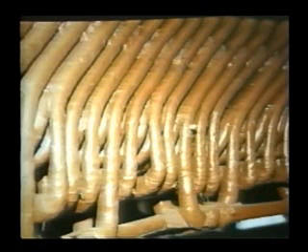Now, the original equipment had an asphalt flake mica insulation system, and this has another type of system which is not thermoplastic and is more mechanically rigid, but at the same time, the question would be, is this stiffness of this insulation system by itself sufficient to warrant the decrease in the number of blocks and ties that were used on this particular machine? Because, as you're well aware, blocking and tying and bracing is a very labor-intensive operation, which requires many man-hours in a large machine, or even a few hours in a small machine, and that can make the difference between the cost being within the limits of what one expects and being excessive.